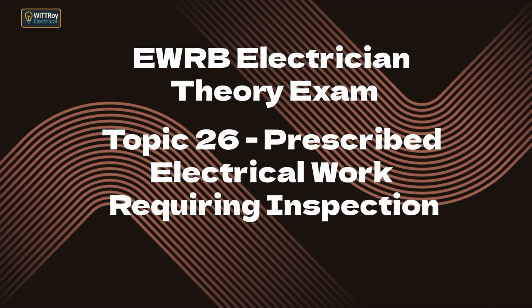The inspection must be done by a registered electrical inspector, not the person who carried out the installation work. 3. The inspector must confirm that the work is electrically safe, the work complies with the regulations, and the work complies with AS/NZS 3000 and any other applicable standards.